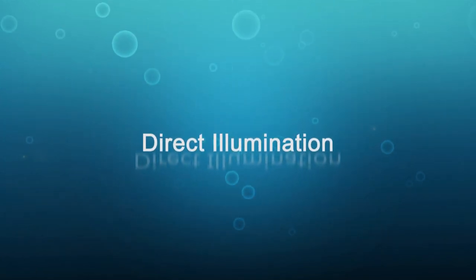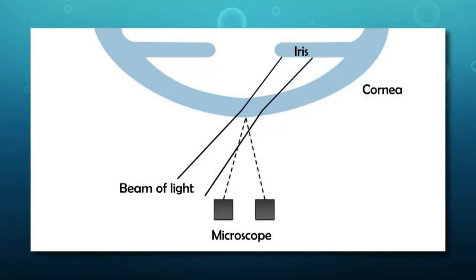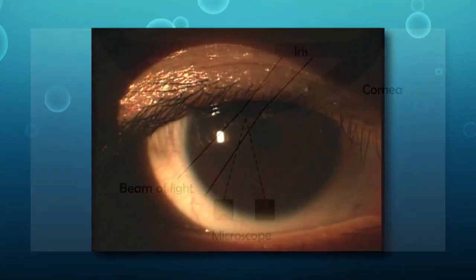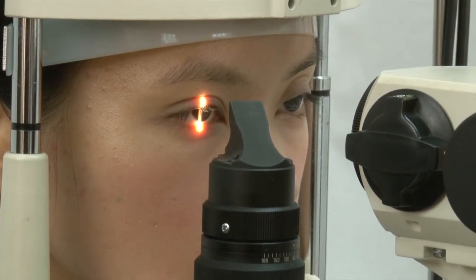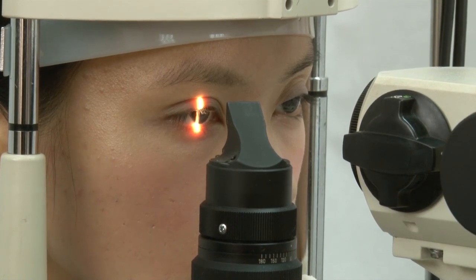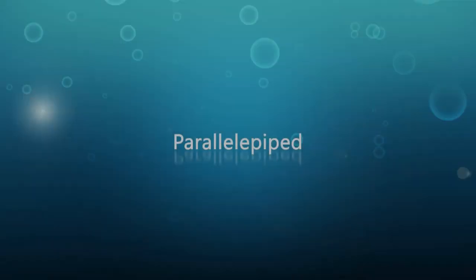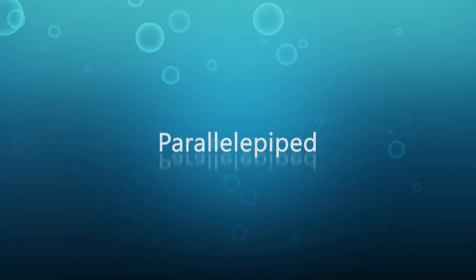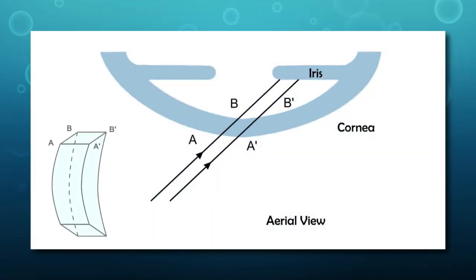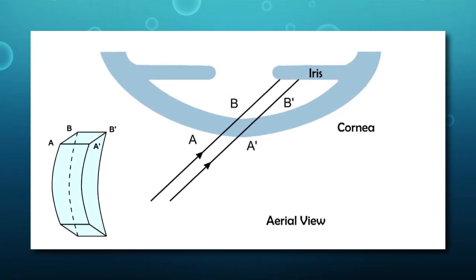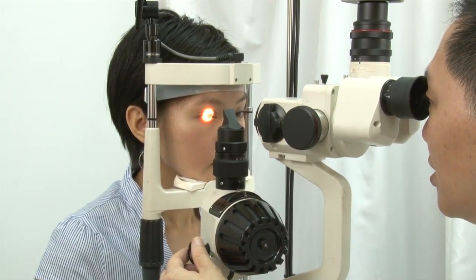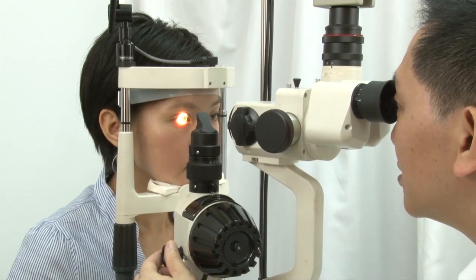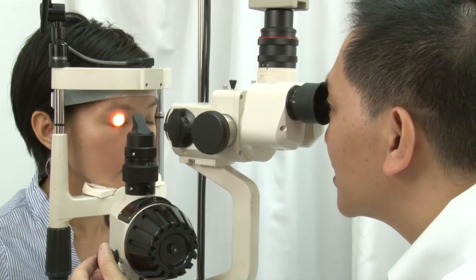The second type is direct illumination, where the light source and observation focus coincide on the same spot on the eye regardless of the position of either system. Direct illumination can be subdivided into the following techniques. The first is the parallelepiped: this technique requires narrowing the wide slit beam to about one to two millimeters. It is useful for a general survey of the corneal layers — for example, the epithelium, stroma, and endothelium — as well as viewing scars, abrasions, and corneal nerves.